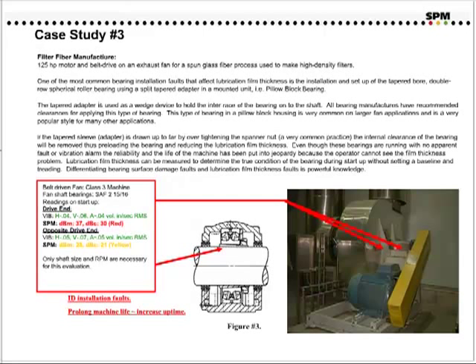Case study number three. This is a filter fiber manufacturer, and the application consists of a 125-horsepower motor on a belt-driven exhaust fan. One of the most common bearing installation faults that affect lubrication film thickness is the installation and setup of a tapered-bore, double-row spherical roller bearing using a split tapered adapter in a mounted unit. The tapered adapter is used as a wedge device to hold the inner race of the bearing onto the shaft. If the tapered-sleeve adapter is drawn up too far by over-tightening the spanner nut, which is a very common practice, the internal clearance of the bearing will be removed, thus pre-loading the bearing and reducing the lubrication film thickness.